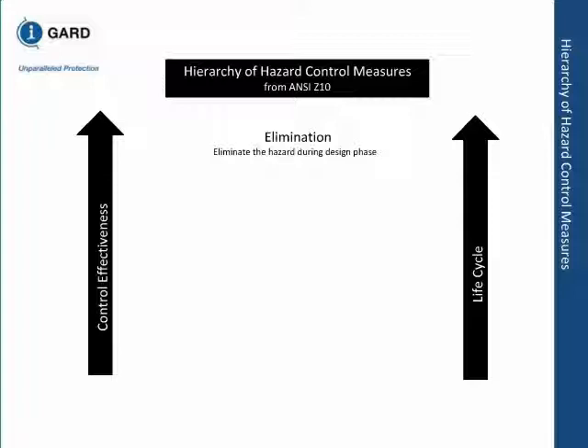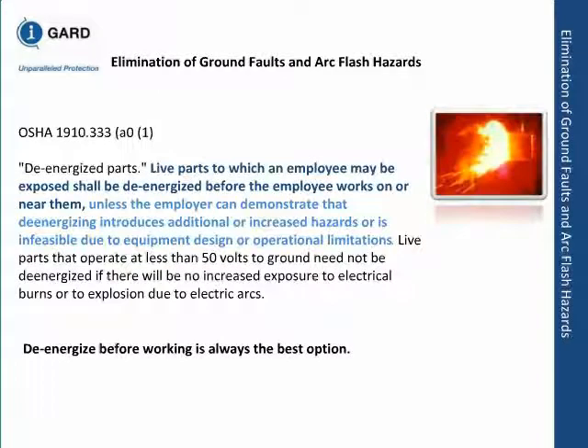OSHA believes in elimination also. This is an excerpt from the OSHA requirement. Live parts to which an employee may be exposed shall be de-energized before the employee works on or near them, unless the employer can demonstrate that de-energizing introduces additional or increased hazard. Keep that in mind, the key words: unless the employer can demonstrate. It's not the employee to demonstrate, it's the employer's responsibility, that de-energizing will introduce additional or increased hazard.